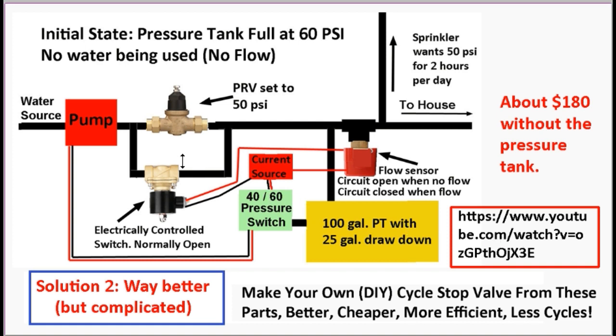But the only thing I want to say about this system is that it solves practically every problem associated with a cycle stop valve. It produces a really good system. It produces high constant pressure and no cycling, and it solves some of the other problems like the pressure dip and rise on first startup and the slow refill rate of the pressure tank. It solves almost every problem. But the thing is, it is somewhat complicated. Carrie Austin referred to it disparagingly as a Rube Goldberg device. So it is a little complicated and probably not for everybody.